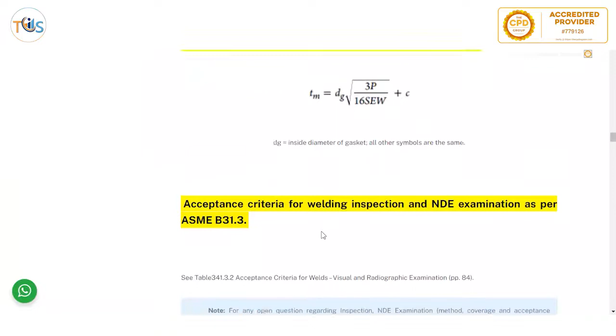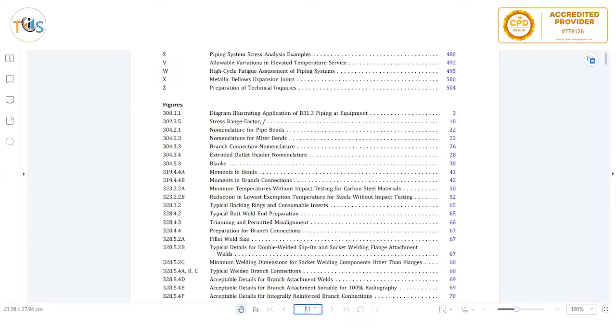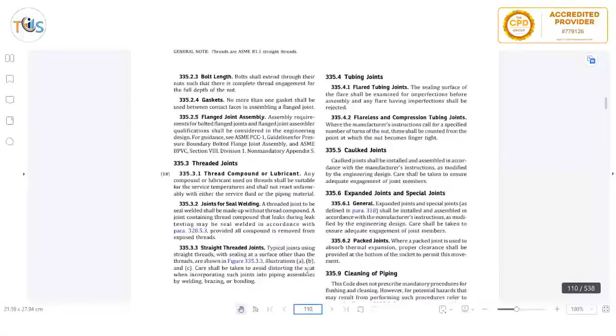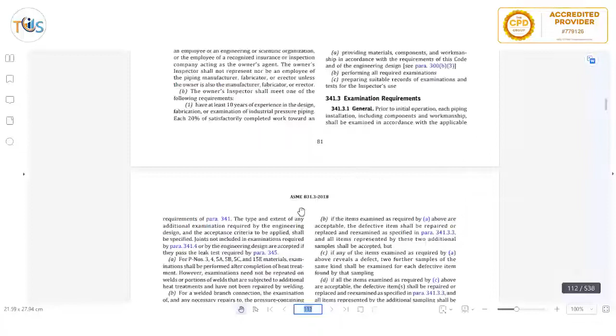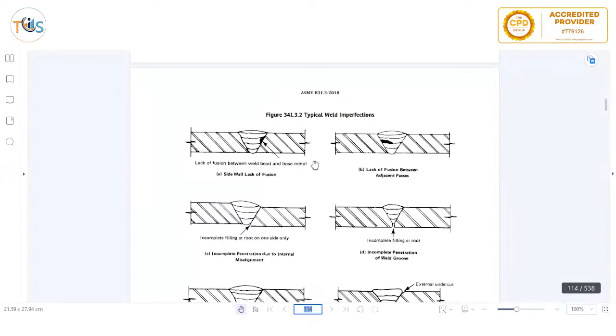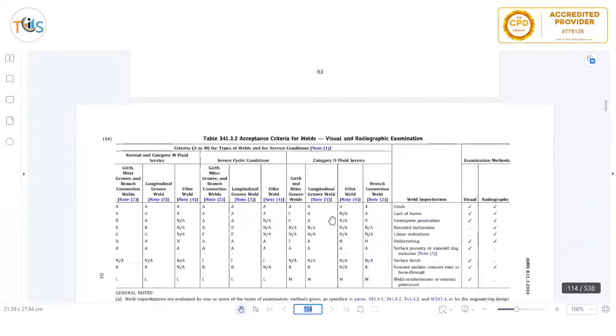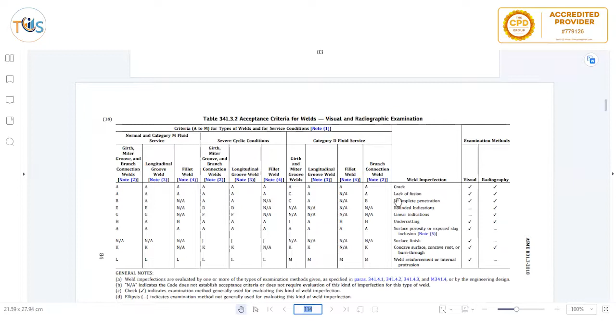Acceptance criteria for welding inspection and NDE examination as per ASME B31.3, and you can see table 341.3.2 as acceptance criteria for welds, visual and radiographic examination. So I just want to show you how it works. So if you go table 341.3.2, let's go and find that table. You can see here typical weld imperfections is telling you what it is, the code, and then you go here, and as you can see, normal and category M fluid service is categorized, cyclic, severe cyclic service, category D fluid service. So if you have a crack, it's A.